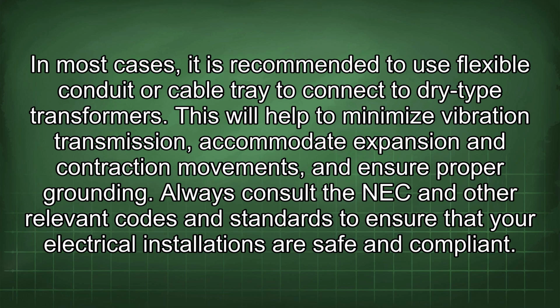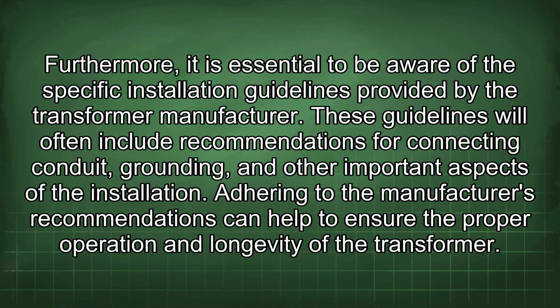This will help to minimize vibration transmission, accommodate expansion and contraction movements, and ensure proper grounding. Always consult the NEC and other relevant codes and standards to ensure that your electrical installations are safe and compliant. Furthermore, it is essential to be aware of the specific installation guidelines provided by the transformer manufacturer. These guidelines will often include recommendations for connecting conduit, grounding, and other important aspects of the installation. Adhering to the manufacturer's recommendations can help to ensure the proper operation and longevity of the transformer.